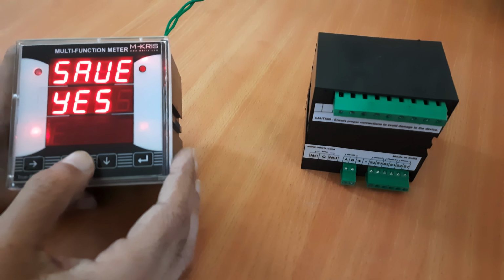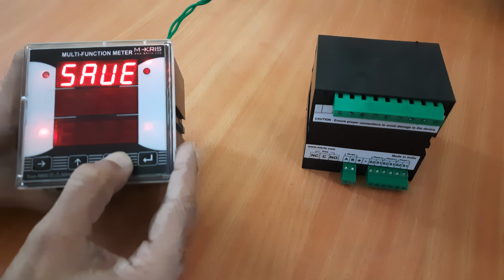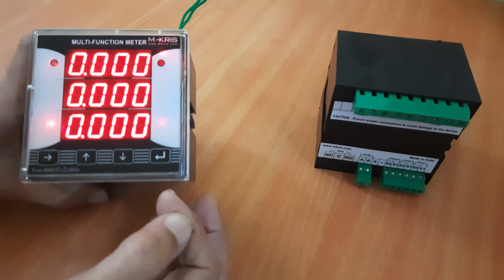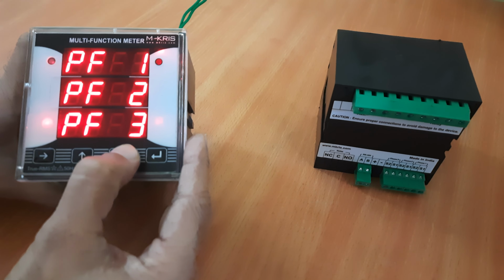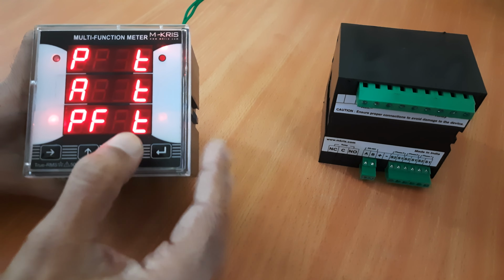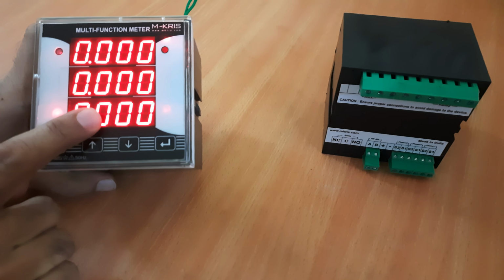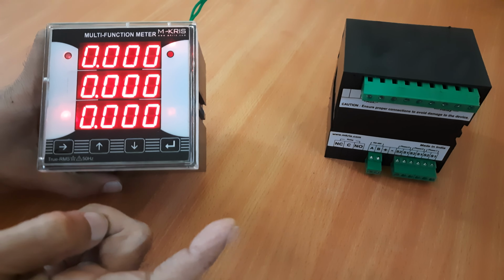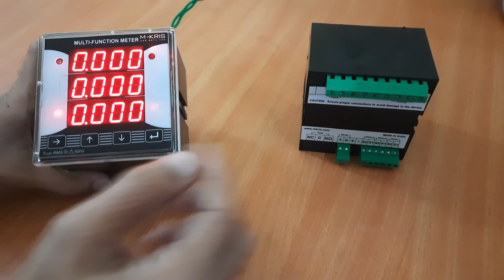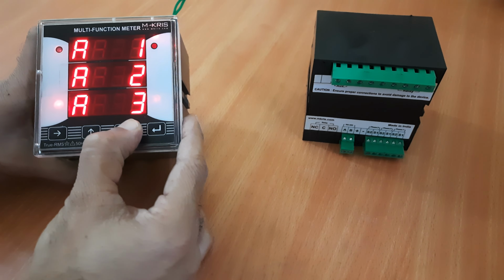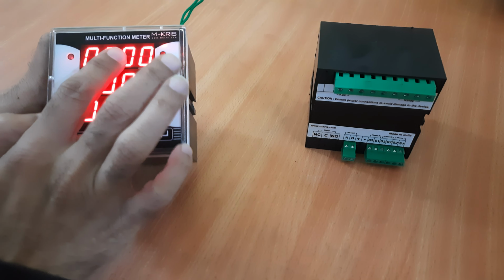And then you have the option whether to save the settings or abort the settings. So this is how settings will be saved. And as we said, just to reiterate, the tripping will depend on any of these phases' power going above the export setting or coming below the import setting. And when the tripping happens, the first line on the first page will show you whether it tripped on export fault or import fault.